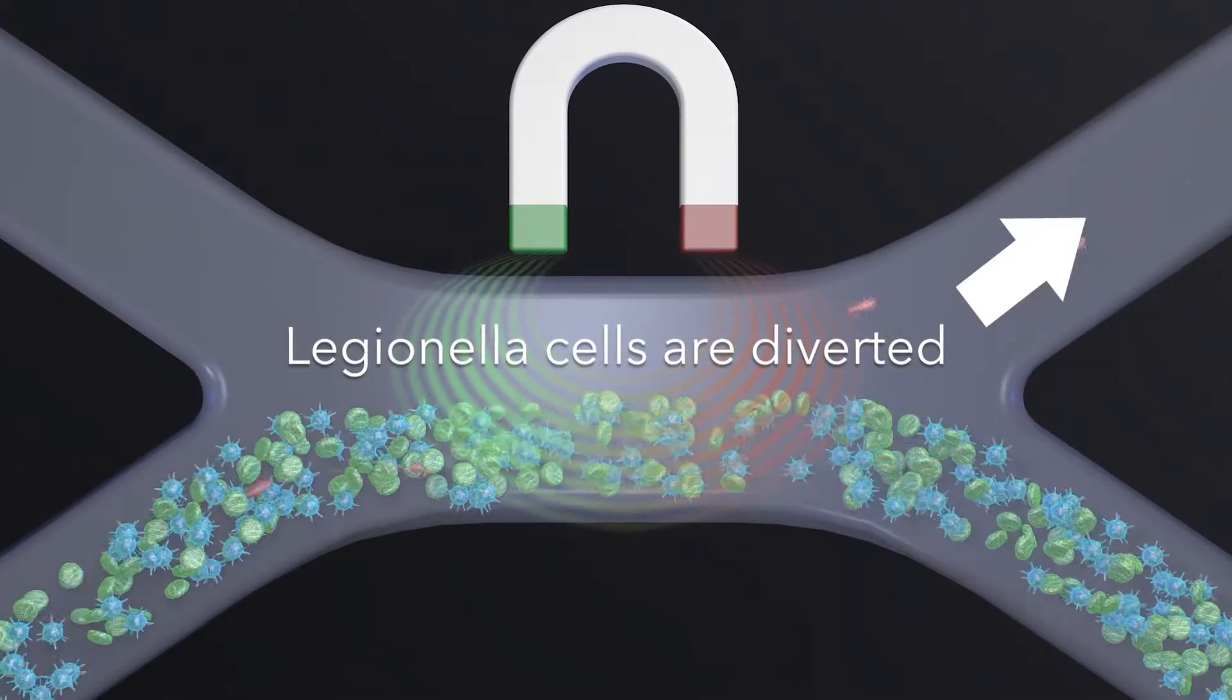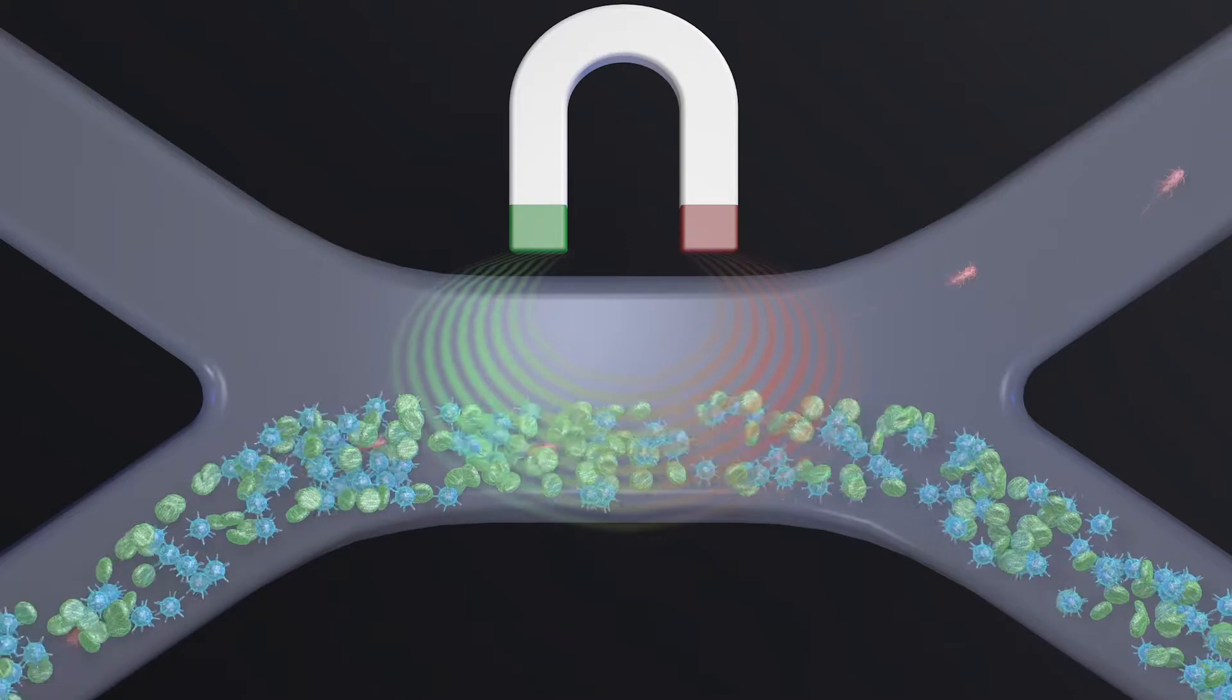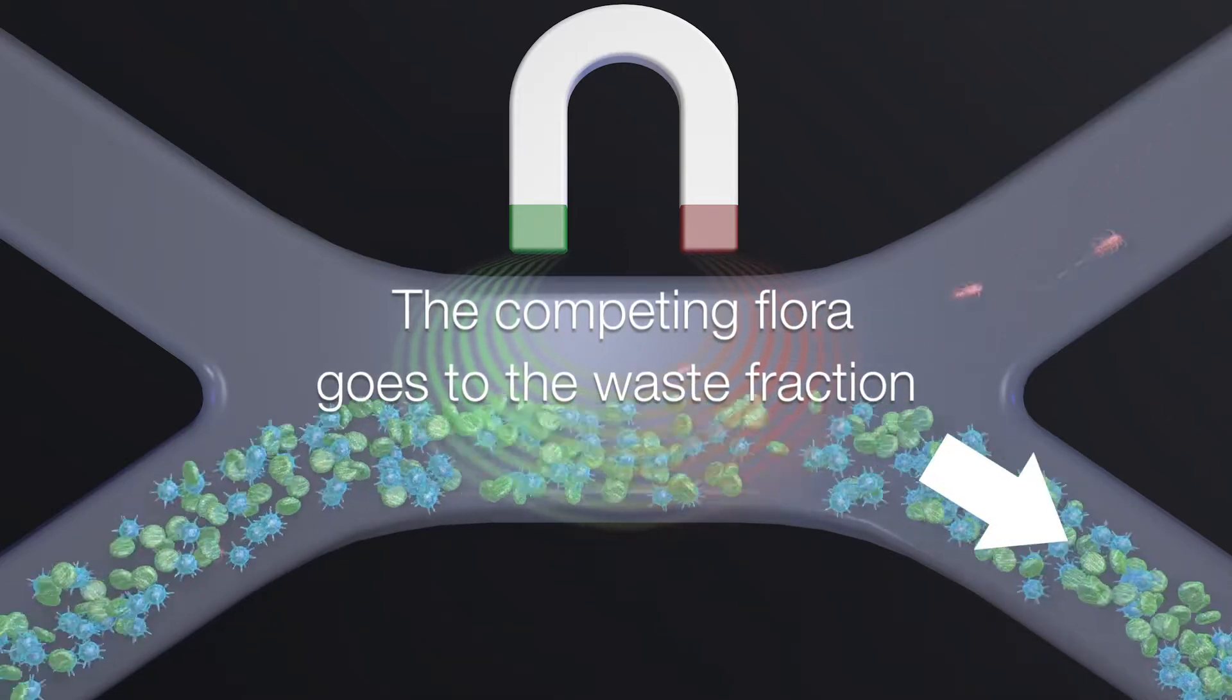The sample passes through a narrow channel in the cartridge. During this process a magnet is lowered down and thereby diverts the Legionella cells which are bound to magnetic particles. At the same time more than 95% of the competing flora originally present in the sample is directed to the waste fraction.